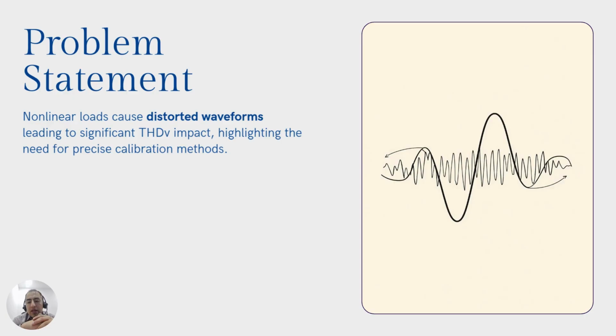This work is about the voltage total harmonic distortion, which visually manifests as a deformation in the pure sine wave, as you can see in our diagram. While network analyzers lack accredited calibration options, on the other hand, oscilloscopes have a wide range of traceable calibration options. So our proposal focuses on leveraging this existing traceability in the oscilloscope to transfer it to the network analyzer, thus closing the metrology gap.